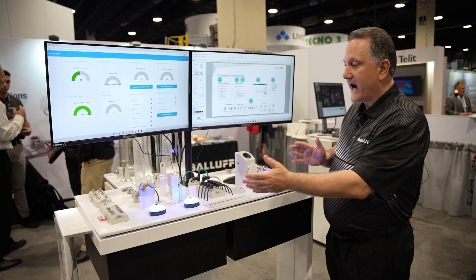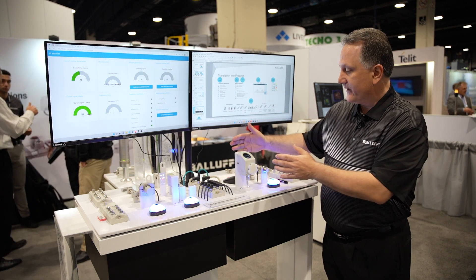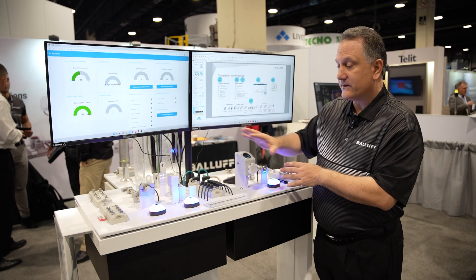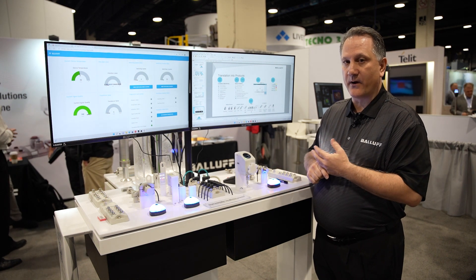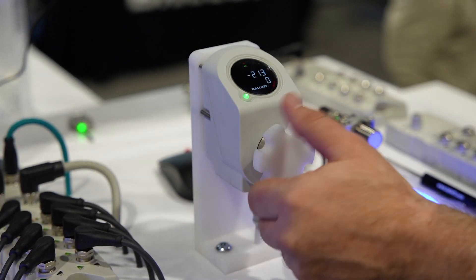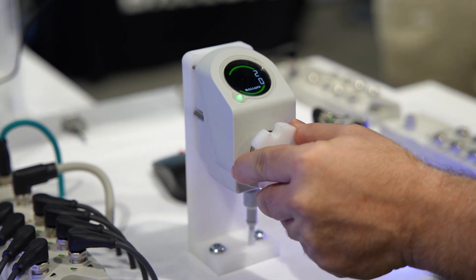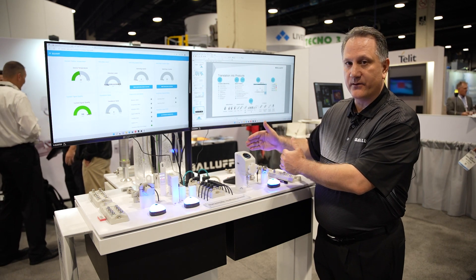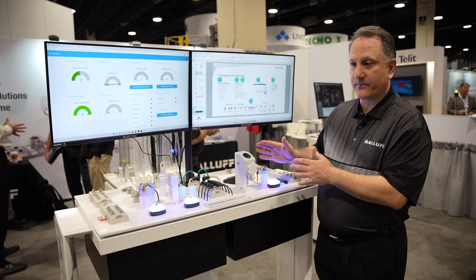There are a lot of different opportunities for application. I'm going to talk a little bit about the digital position indicator. Here we have a rotary position sensor, and all of these devices are IO-Link, so you have the ability to dynamically change parameters. With the digital position indicator, it works really great on hand cranks. We have a digital display showing the operator the direction to turn, what the set value currently is, and what the target value is, helping to guide the operator to change the hand crank into the correct position.